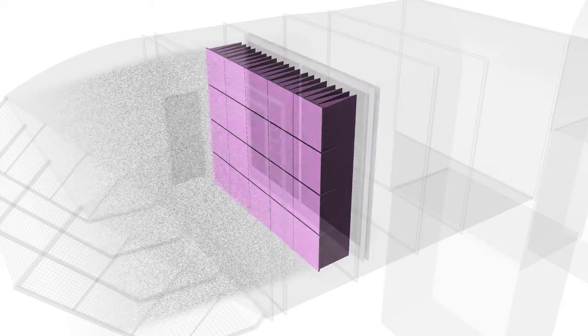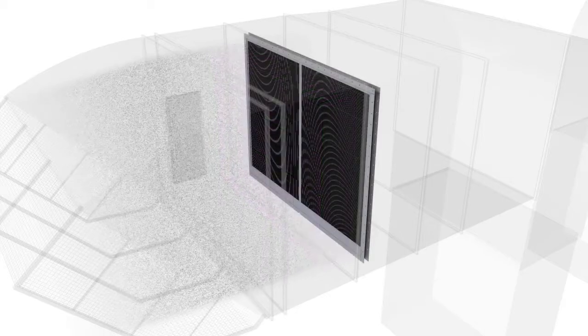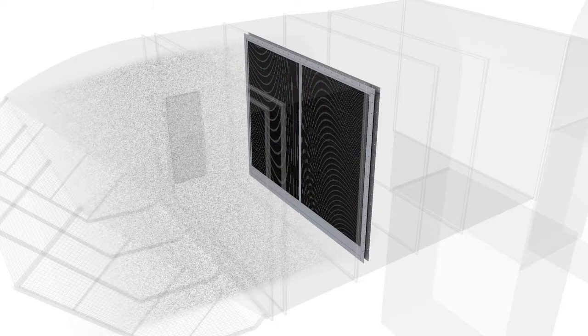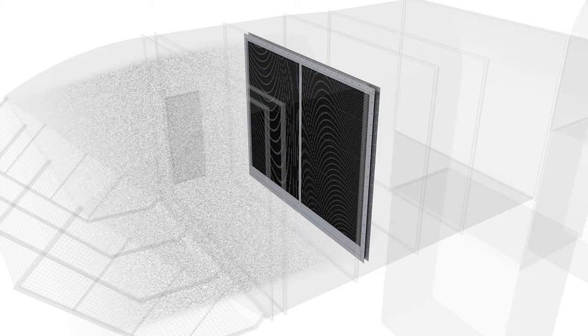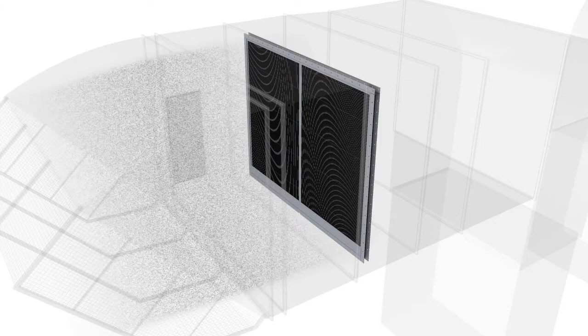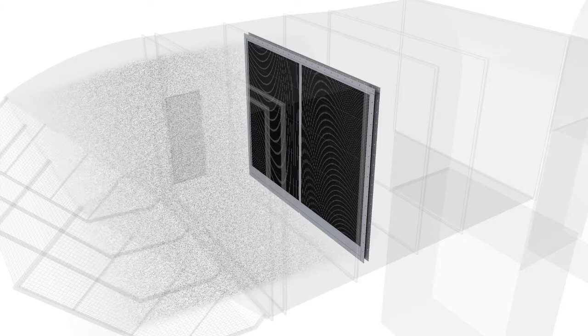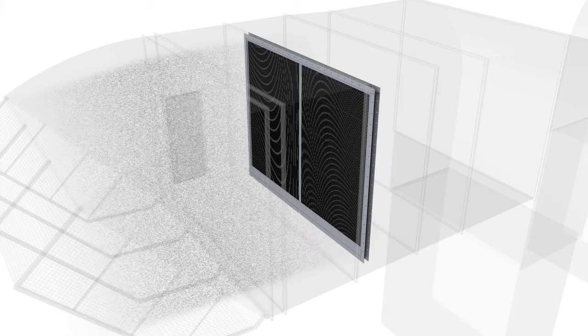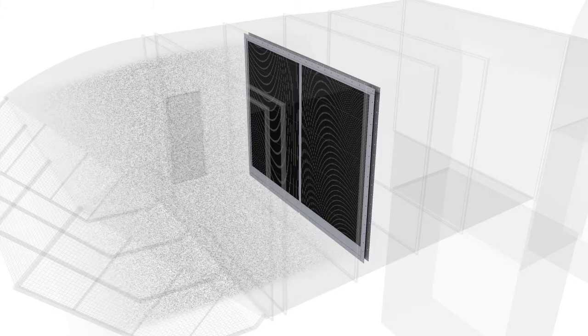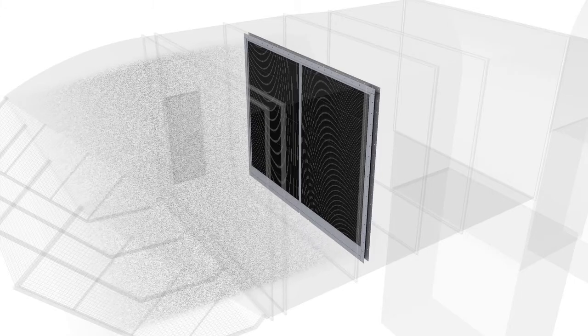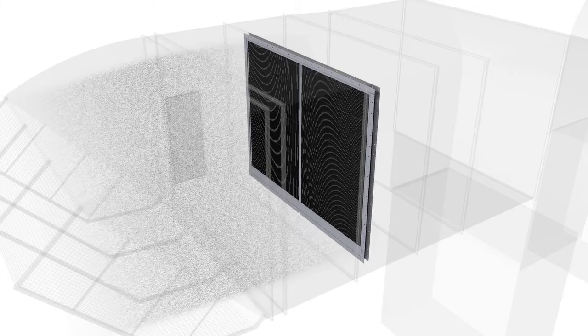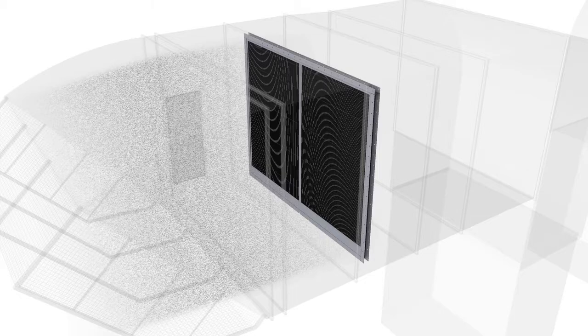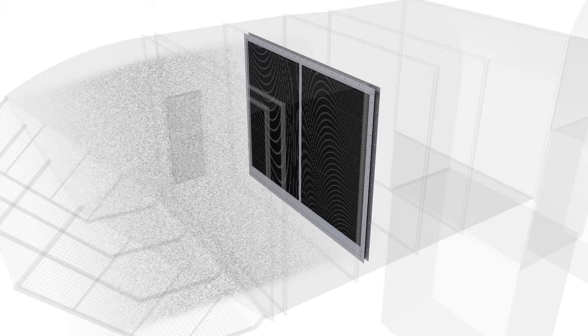The fourth and final stage is another vane separator. Similar in design to stage 1, this inertial separation stage not only captures re-entrained liquid but completely removes it from the inlet by a manometrically sealed drainage system.